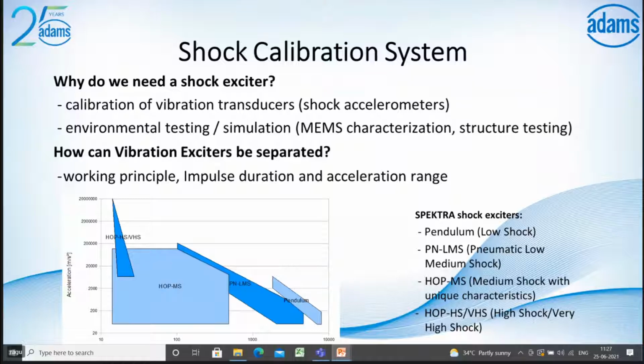So why do we need a shock exciter? That is for the calibration of shock accelerometers and environmental testing, such as structural testing and MEMS characterizations. How can we separate the exciters? Based on the working principle, the acceleration range and the impulse duration. Spektra is offering a low shock system, which works based on the simple pendulum method, and LMS, that's a pneumatic low medium shock, using the pneumatic method for the calibration, and HOP, the Hopkinson method, for the medium shock, HOP for the high shock, and VHS, that's a very high shock. So these are the principles behind the shock calibrations.